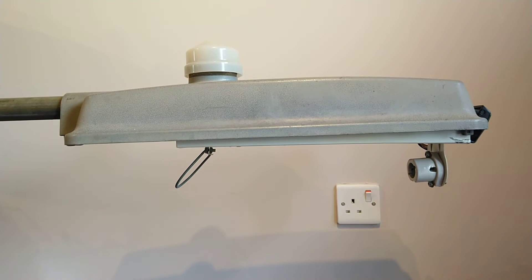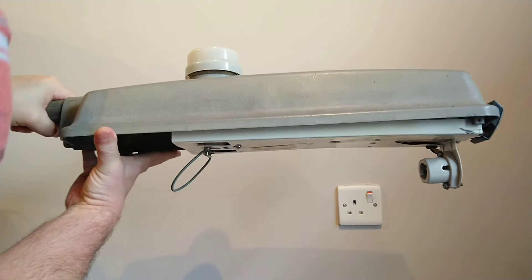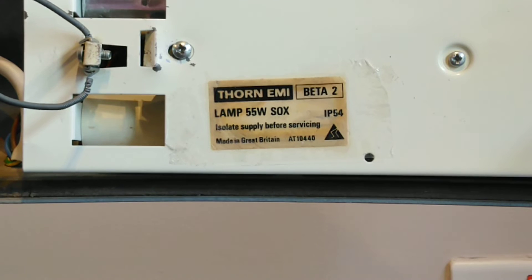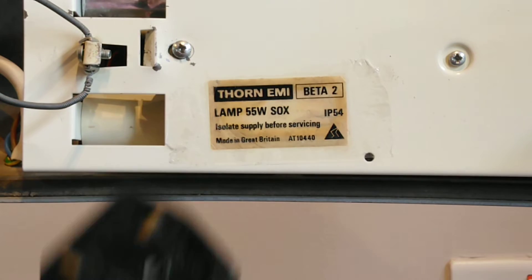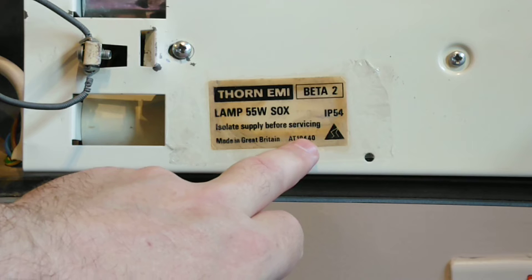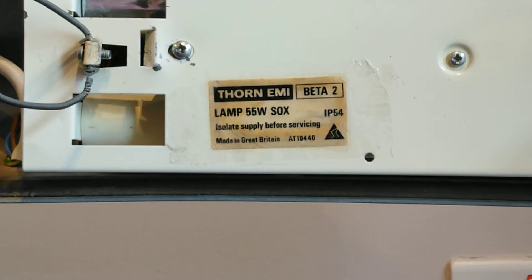There is also a hint of mercury and some other gases including neon in these lamps. Now I'm going to turn this light on its side, as they do on street lights when fixing them, and zoom in so you can see the sticker inside. It says 'Thorn EMI Beta 2', the lamp it requires is 55 watt SOX, and 'isolate supply before servicing'. I've already done that. It's made in Great Britain, and IP54 means it's rated for outdoor use.